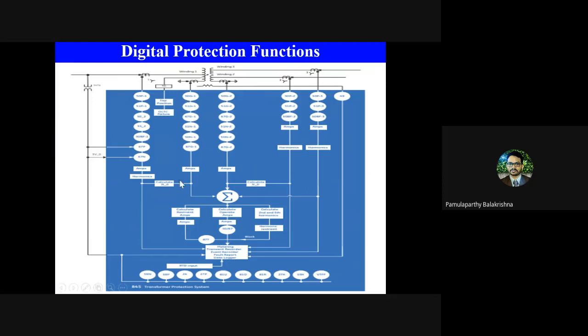Okay, so essentially all the protection functions are either related to current, voltage, frequency, or power based protection functions, and sometimes you have distance and differential protections. Okay, so for each of the protection functions, the corresponding input should be available as a signal input to the relay. So as long as the signal inputs are available, those functions will automatically run, and those functions will be executed inside the protection relay.